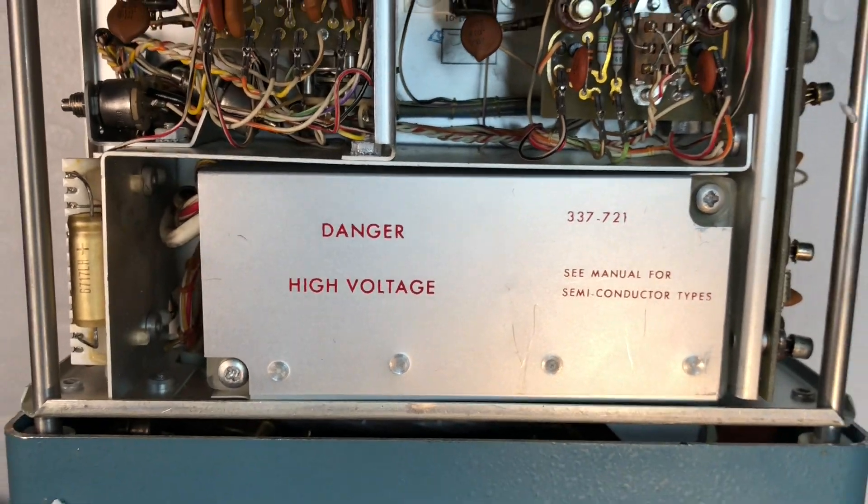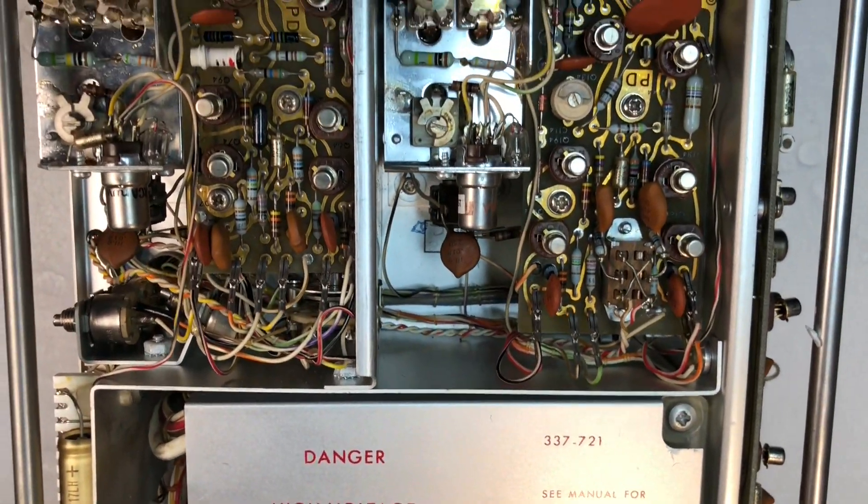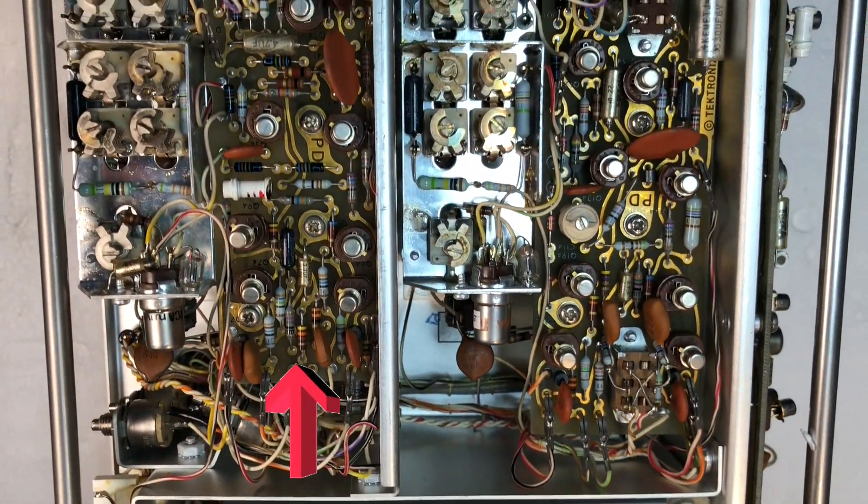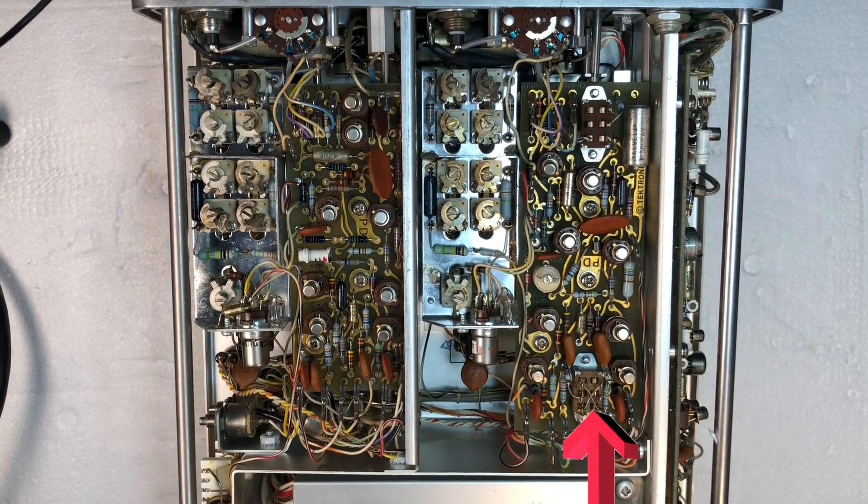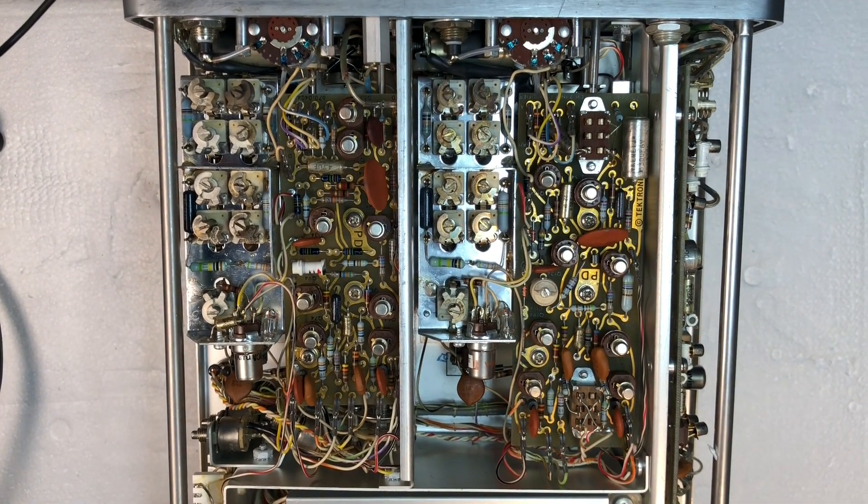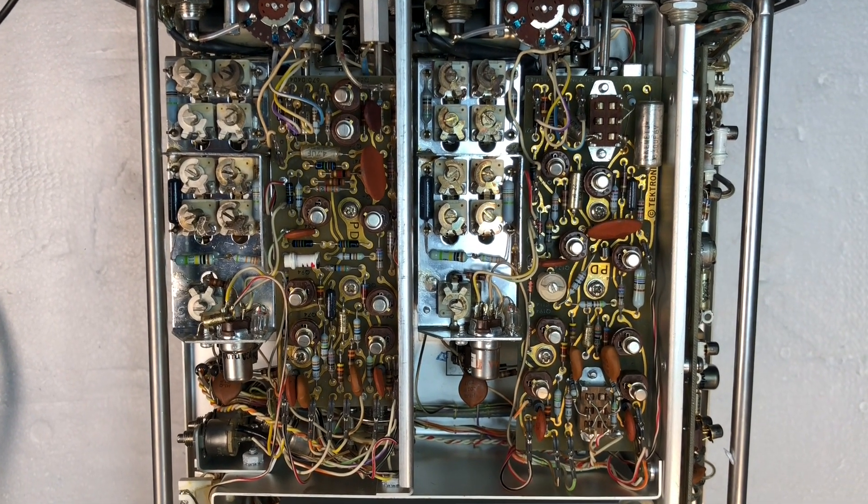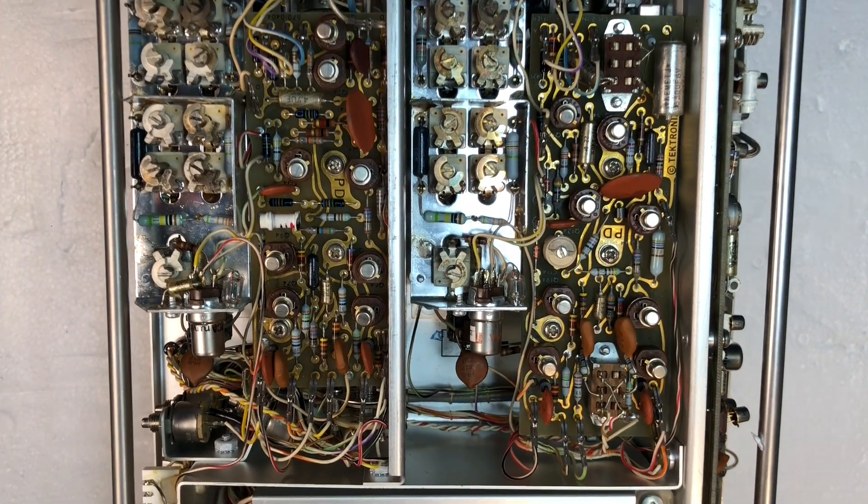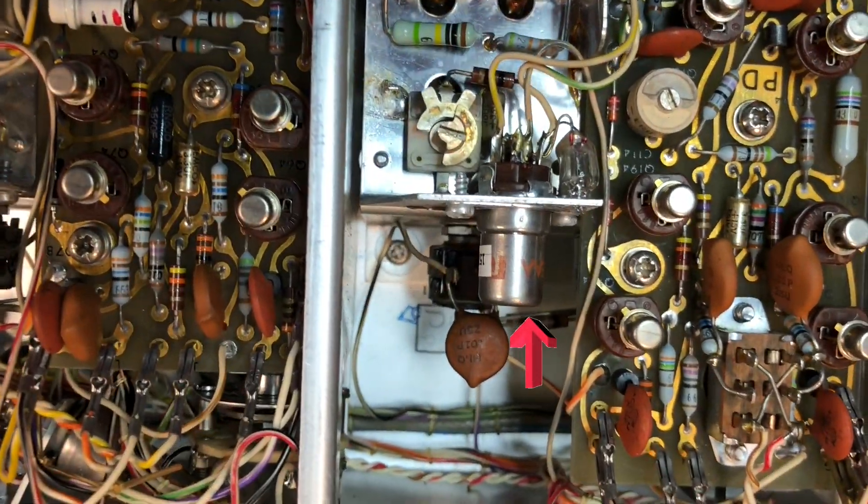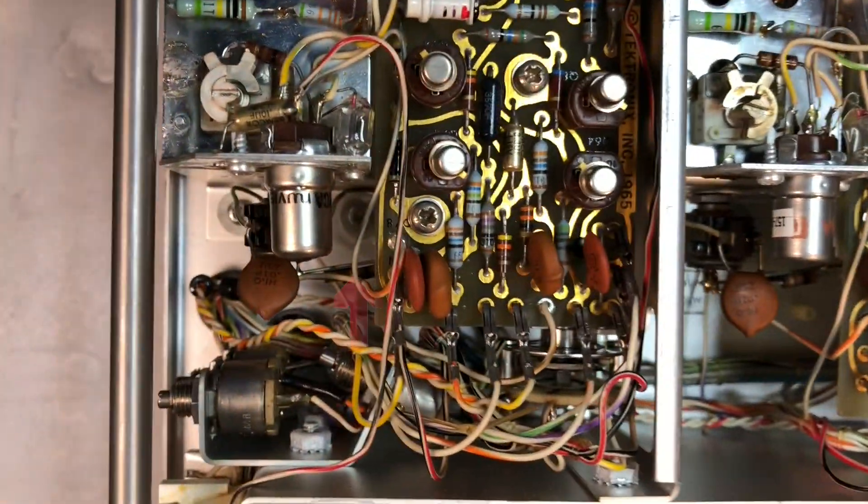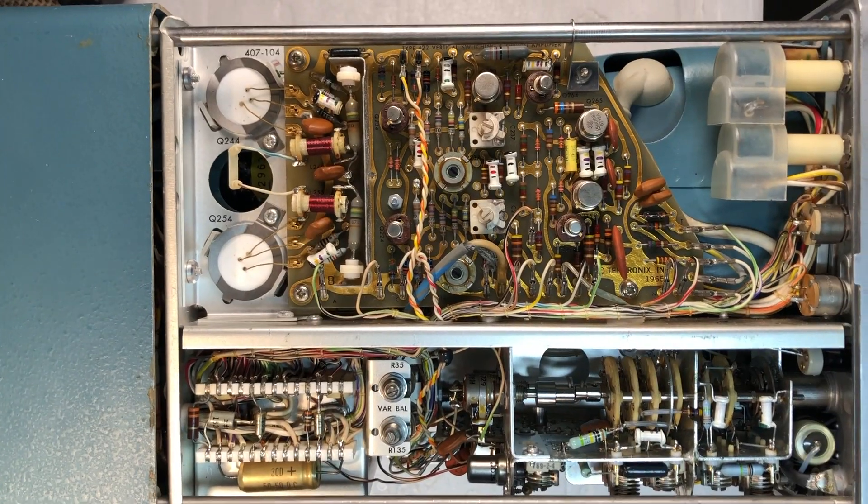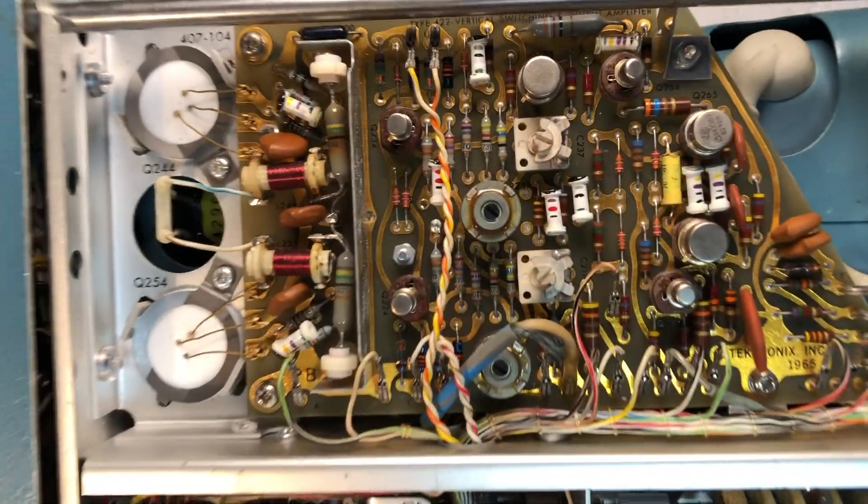The high voltage cage which we removed earlier, and the two input pre-amplifier boards for both channels. There is a pre-amplifier board which is the attenuator plus the front end, and you can see the nuvistors here for each channel.